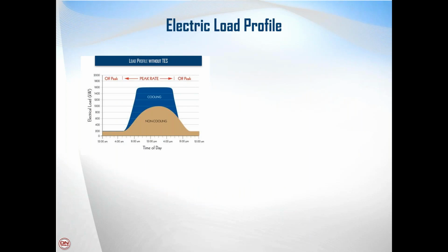Electrically, let's look at how a thermal storage tank helps the owner reduce their electrical costs. A typical electric load at a facility or a campus looks like a bell-shaped curve. On here, you can see the bell shape of the electric load rise up during the day. And a lot of that electric load during the day is due to the cooling system. That's because the campus is now being occupied and it's warmer in ambient conditions outside, so their space cooling requirement goes up. And so there's more electric load during the middle of the day.